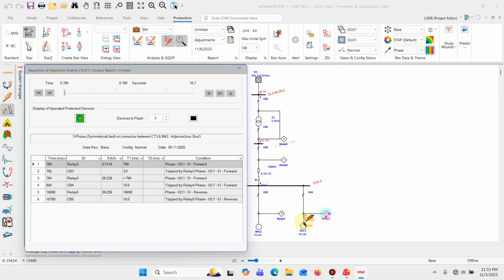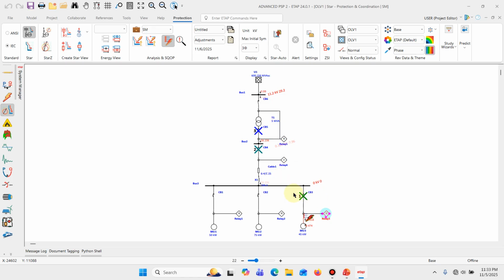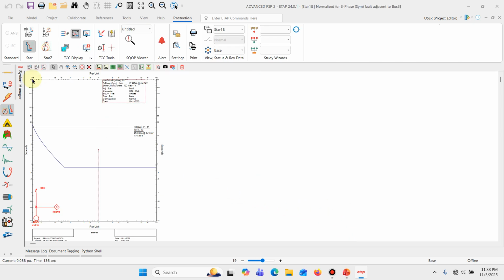Now, we mentioned some parameters. We said selectivity is 1. Aside from looking at the system, we can tell that this system is good in terms of selectivity because the coordination sequence looks good, allegedly. Now we come over here and we look at the time of operation. We can see that this relay is taking 789 milliseconds to operate. So it is at this point we now need to checkmate this by creating a TCC with that relay to see how the system operates.